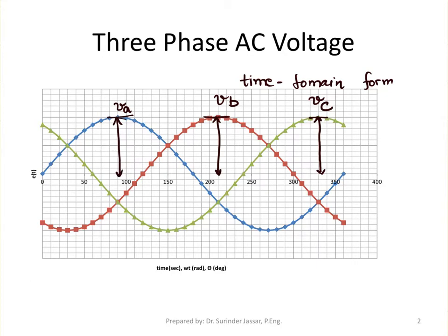Now the phase angle. You can see that A has a phase angle of 0 degrees. For B, each square is 10 degrees, so this is 120. B is lagging behind A by 120. That is how we can say it has an angle of negative 120 once we draw it on the phasor diagram.